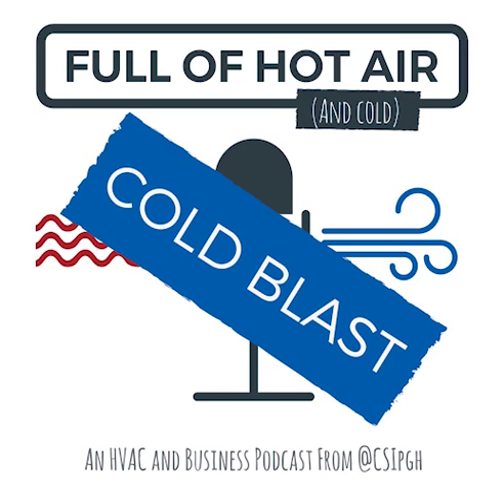Traditionally, a 6-inch round duct run, which is very commonly used in most homes in our area, provides about 100 CFM. So you want to at least see 12 of those in a house, or bigger sizes like a 7 or 8-inch equivalent if it's rectangular duct. First off, to get an idea of what your airflow is going to be, look those things over and get a count. From a mental perspective, that's just getting yourself in the ballpark of where you think the airflow is going to come out.